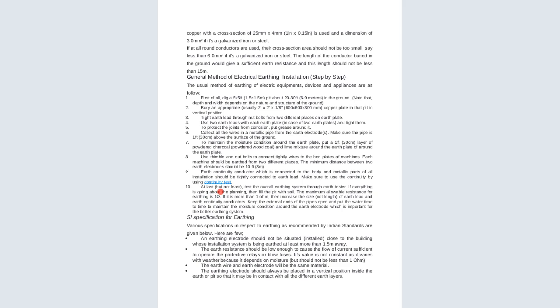At last, step 9 is the earth continuity, which is connected to the body and metallic part of all the installation, and should be tightly connected to the earth lead. Now make sure to check the continuity by using the continuity tester. And then the last step is to test the overall earthing system with the earth tester. We normally have an earth tester, and this earth tester is also called an earth loop impedance tester. So if everything is going according to plan, then fill the pit with soil.